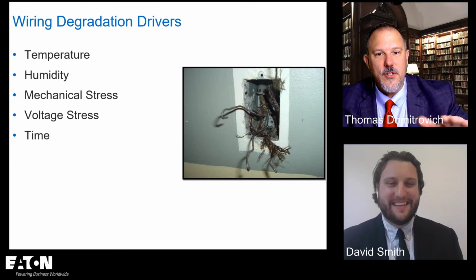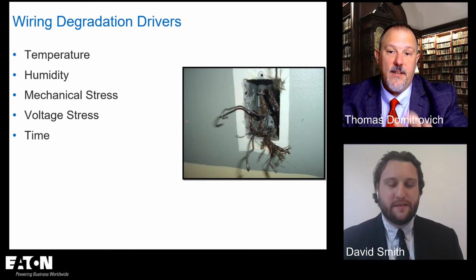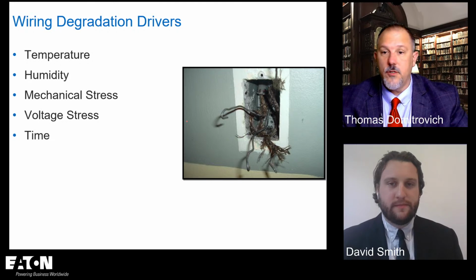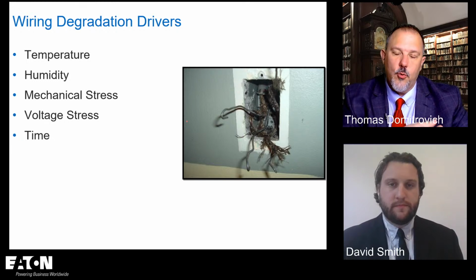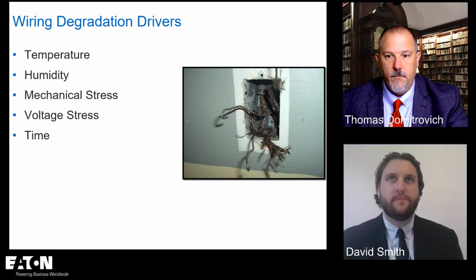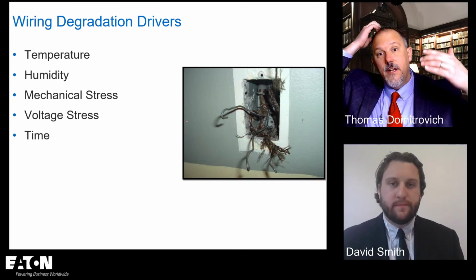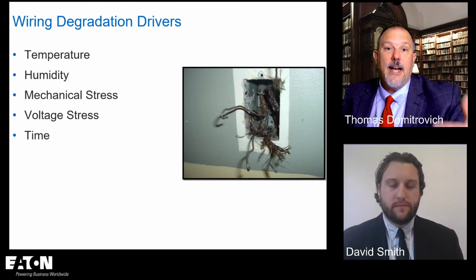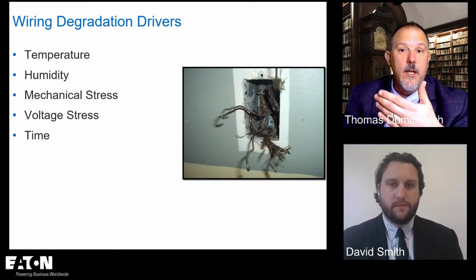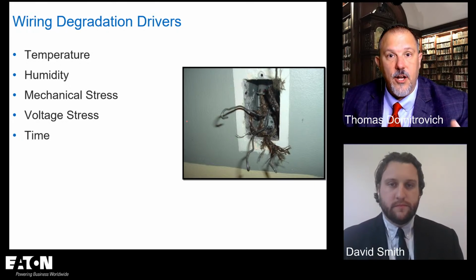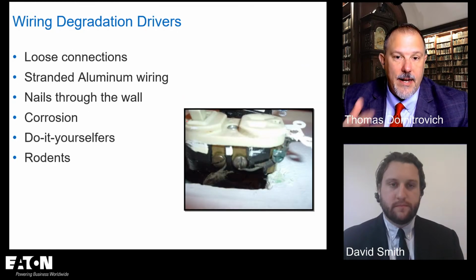So this is a picture that was detected by an AFCI in my brother's house. It was an older home, retrofitted into an older home. So another thing to remember, I don't need an equipment grounding conductor for this to work. Right. So I can have knob and tube wiring, and I can provide protection. I can have the older wiring like this, that does not have an equipment grounding conductor associated with it. It has just a hot and a neutral. All right. So I can provide that same protection.